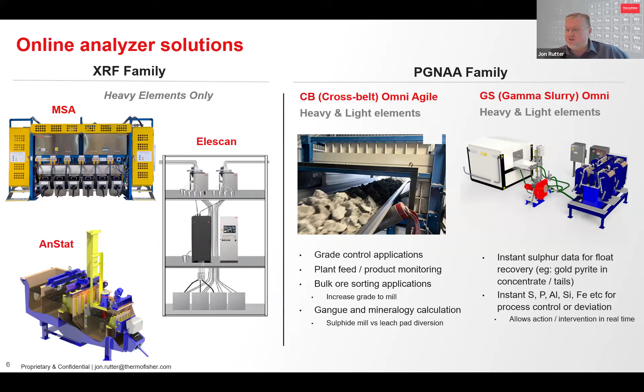But in saying that, I also want to highlight, don't fix what isn't broken. XRF analyzers, they're a tremendous tool and they will meet a vast requirement of your business needs. They're quick, easy, reliable, and they'll work perfectly well. But if your business needs actually go beyond the remit of what XRF is capable of delivering, then you may need to look at PGNAA analyzers. This means your area of opportunities may include light elements like silica, phosphorus, sulfur, for example, or light elements and heavy elements, but in a location that XRF can't operate.